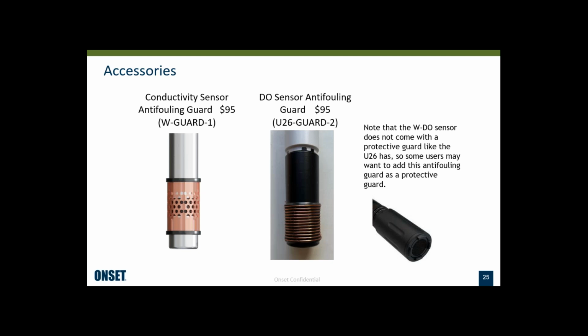The anti-fouling guard for the DO sensor is actually the same one that we're already selling for the U26. So that's a screw-on guard, and it's real easy for the user to attach and remove as needed for cleaning the fouling. The one thing I wanted to note is the DO sensor has a guard that holds the cap on it, but it doesn't provide as much protection as the U26 guard. The membrane's actually exposed here, which makes it easier to clean, but it makes it a little less protected. So some users may want to buy this anti-fouling guard as a protective guard for the DO sensor. Even if they don't need the anti-fouling, it still provides some added protection.